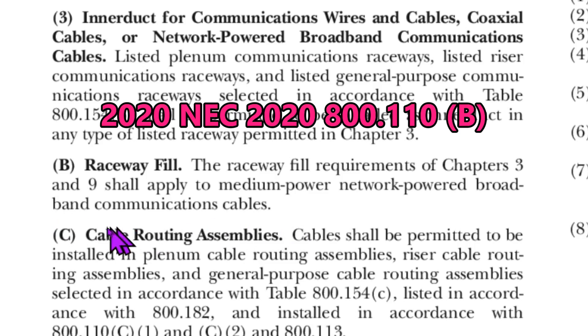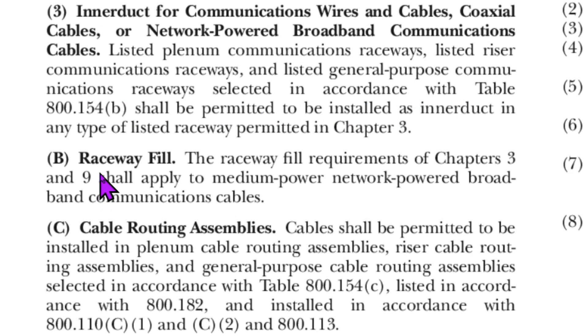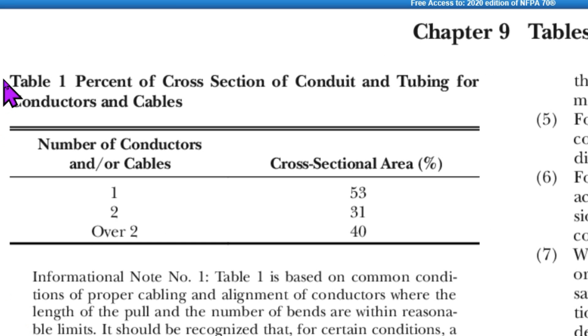With the expanding use of power over Ethernet. Let's check out the new 2020 NEC code. And let's find something that might help us pass inspections. So here is Article 800.110B, Raceway Fill. The Raceway Fill requirements of Chapter 3 and 9 shall apply to medium power, network powered, broadband communications cables. And here in Chapter 9, here's Table 1, percent of cross-section of conduit and tubing for conductors and cables. So in a conduit like EMT, you would put several Ethernet cables in it. For over two, your cross-sectional area is 40%. So you can't go over 40% of your conduit filled with Ethernet cables.